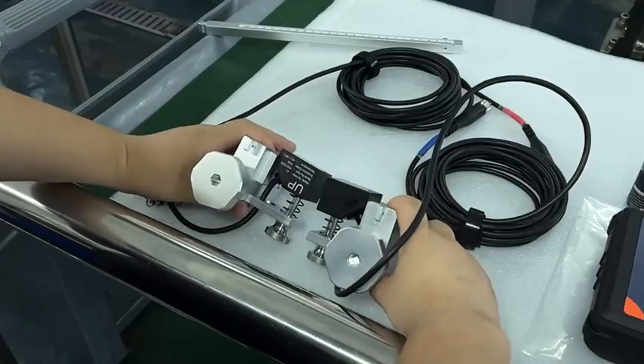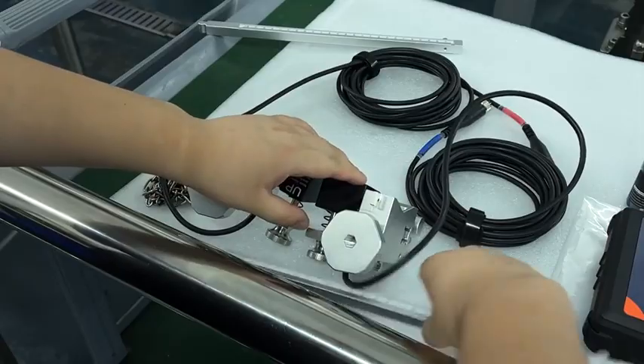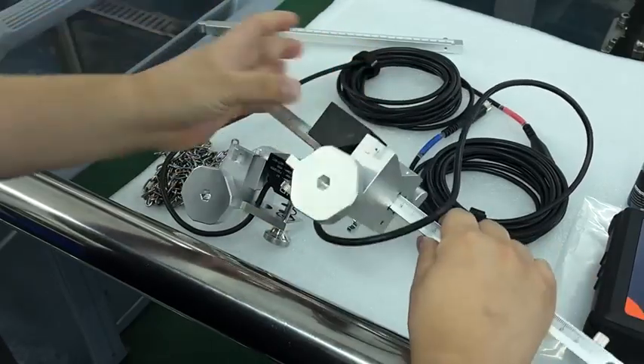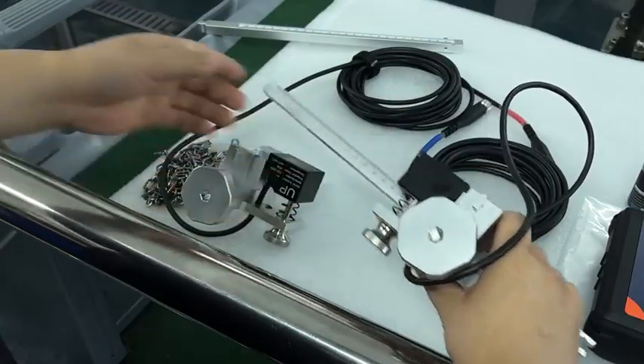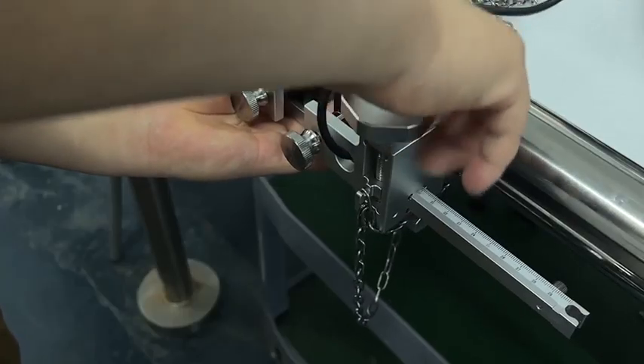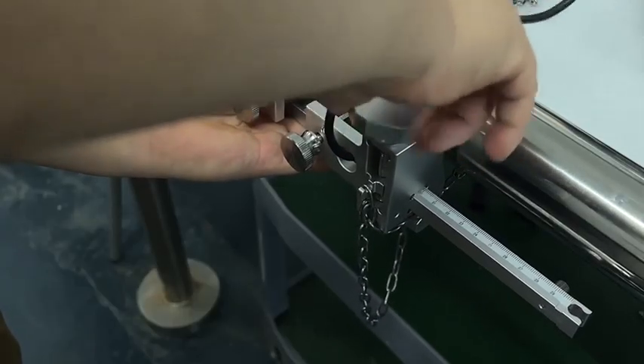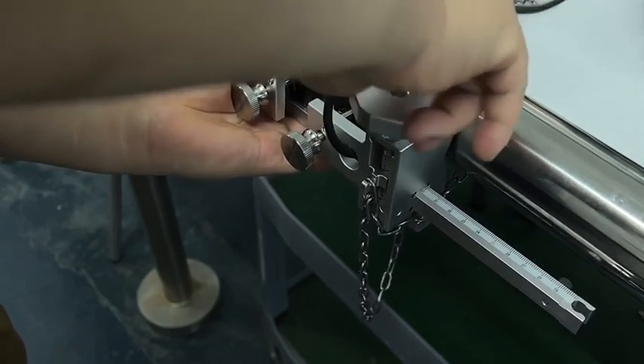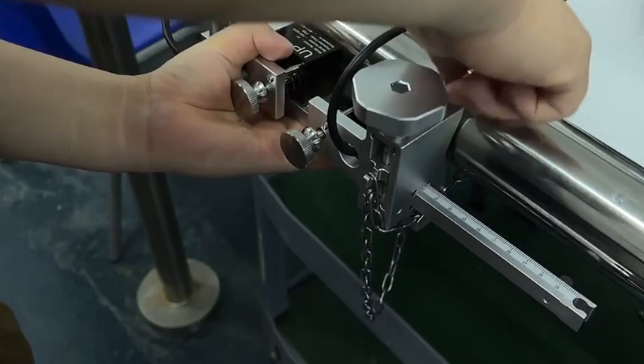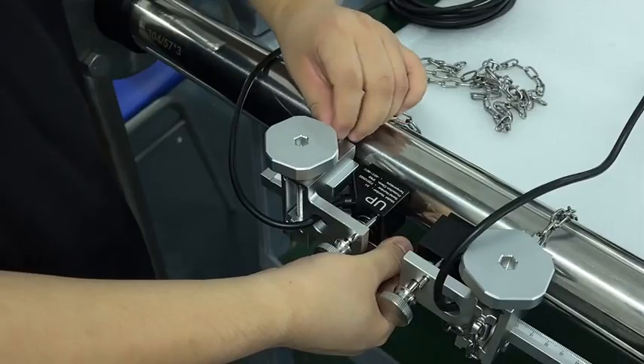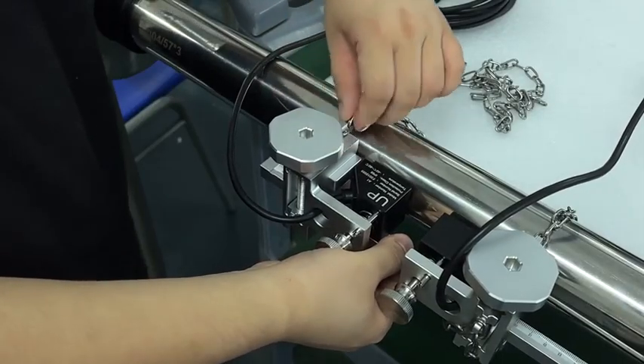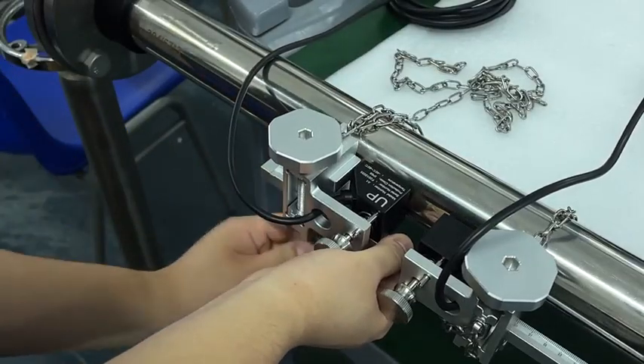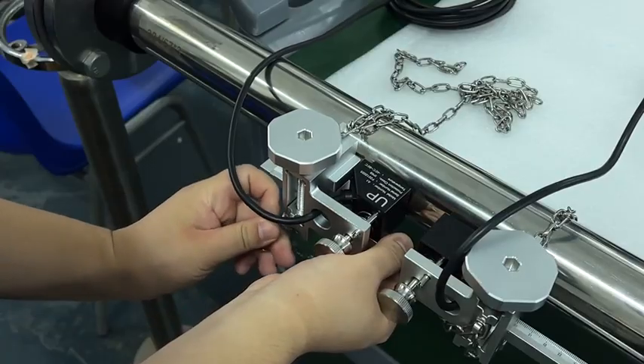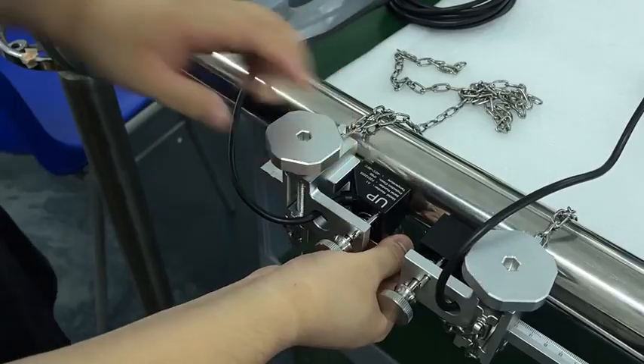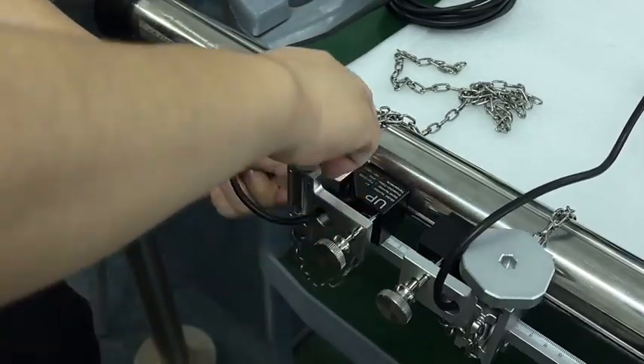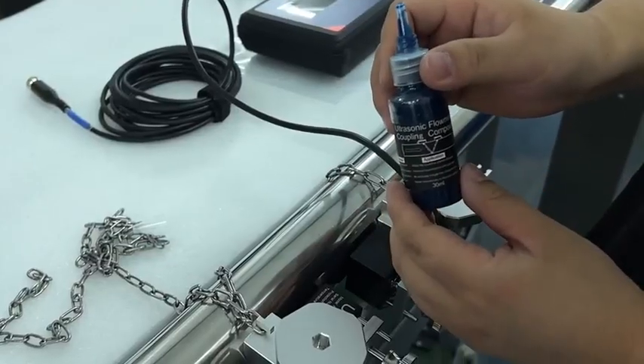Sensor installation starts with bracket assembly. The bracket holds the 2 transducer probes in a fixed geometric relationship positioned along the pipe at the correct angle and spacing for the pipe diameter being tested. Getting this geometry right is the single most important step in achieving accurate measurement. The chain is then wrapped around the calibration pipe and secured through the bracket slots. This chain and bracket system is the same hardware that end users receive. It installs without tools, without cutting the pipe, and without shutting down the process. Installation on most pipe sizes takes less than 10 minutes.